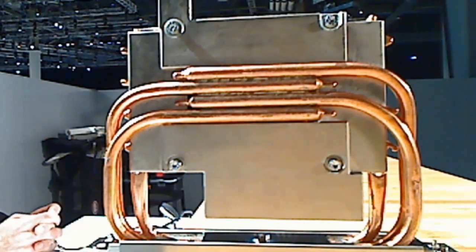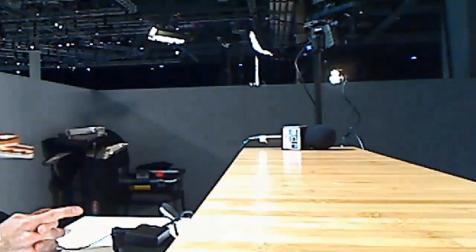And when I say dry disconnect, one of the ways to solve this is, if you look inside our Apollo 8000 system, there's a water wall. There is literally a wall of water that has cold air blowing on it, and what ends up happening is this is attached to that wall of water, so we refer to it as a thermal bus bar, and on top of that are cooling coils. There's a very small amount of liquid in here, it's under vacuum, and this would attach to the top of the processor. So the bottom line is that not only were we able to deliver tremendous performance, not only were we able to deliver it in a unique liquid cool scenario, but the beauty is, working with NREL, we're able to save them $1 million worth of OpEx and CapEx costs.